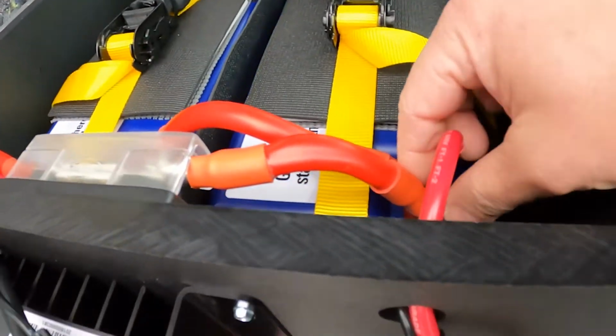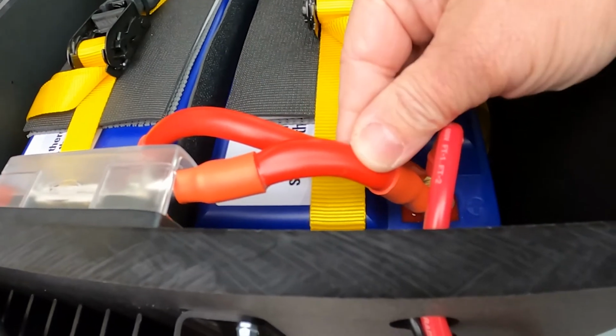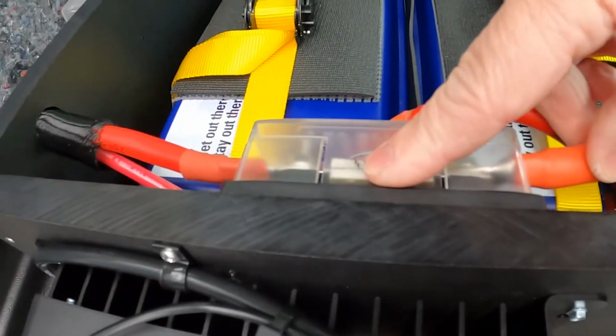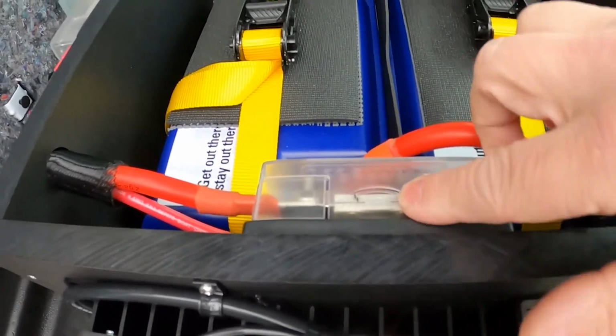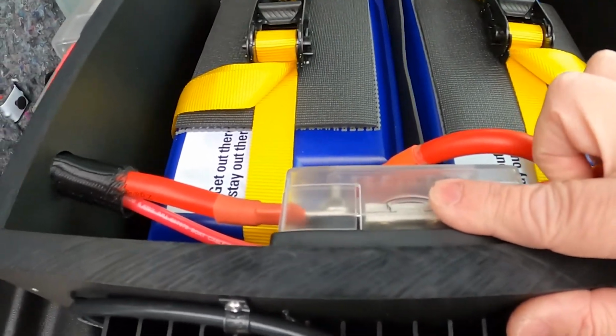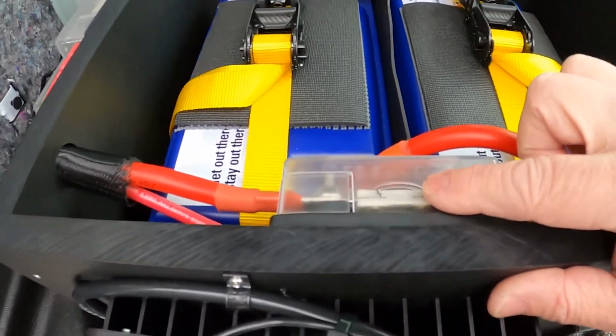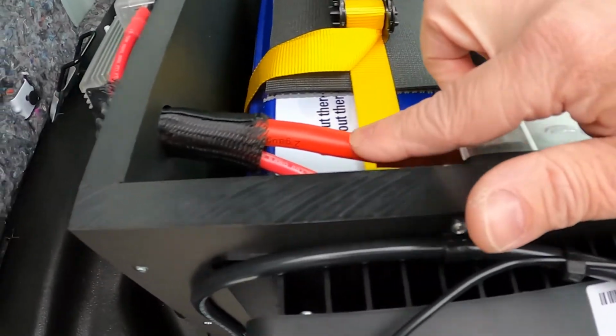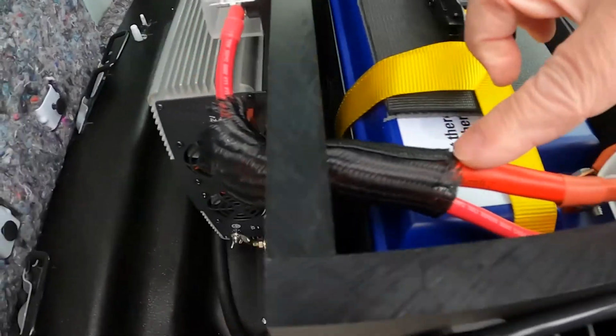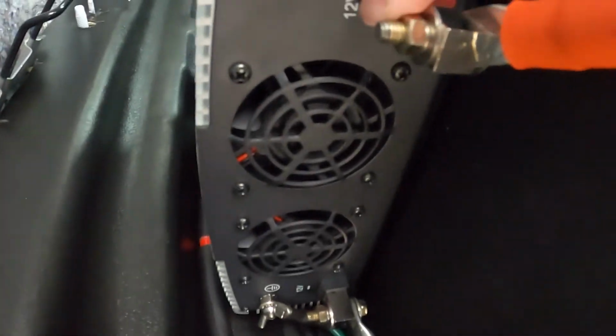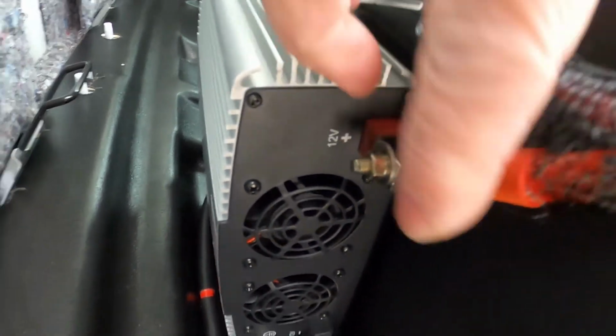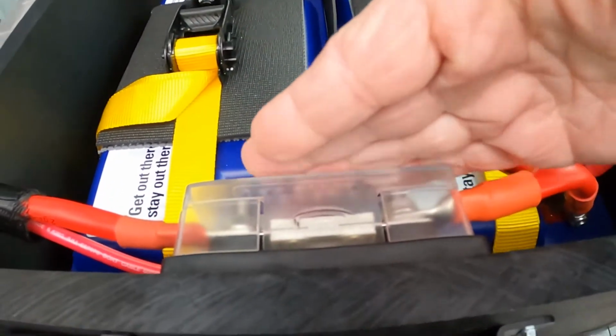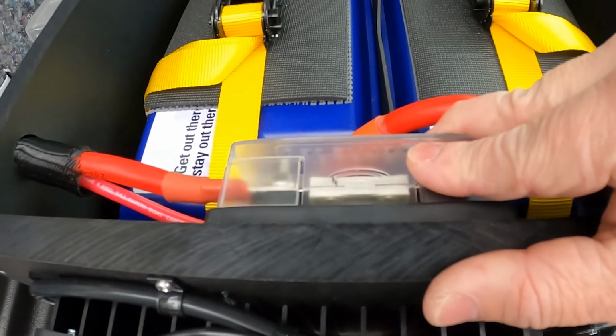So I have, for example, a 2 gauge cable connected here. Currently I'm using a 200 amp ANL fuse - I may bump up to a 225 if this blows. Then this comes out and terminates right here on my inverter. This fuse is dedicated to the inverter.